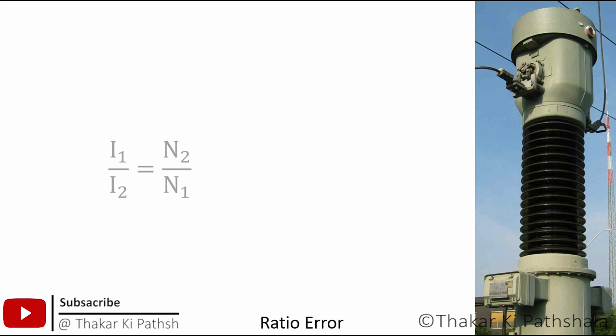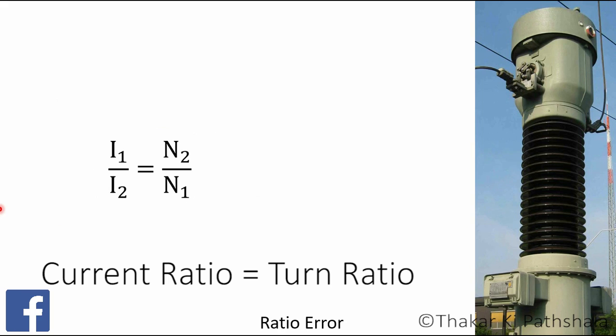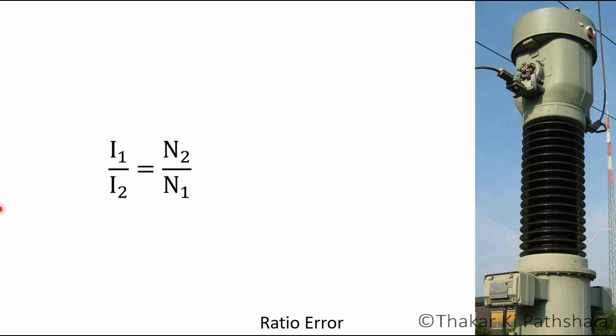Let's take a look at ratio error. We all know this famous transformation equation for any transformer, which is I1 divided by I2 is equal to N2 divided by N1. So theoretically current ratio should be in proportion to the turn ratio of transformer. But in practice, it is not so.